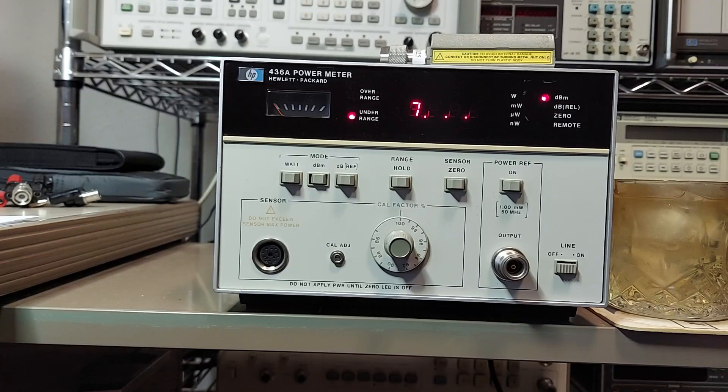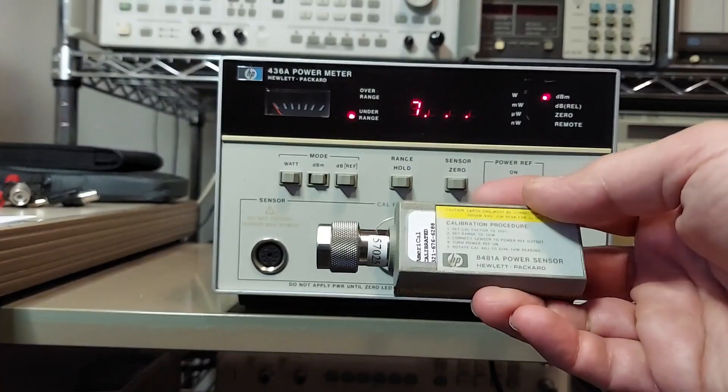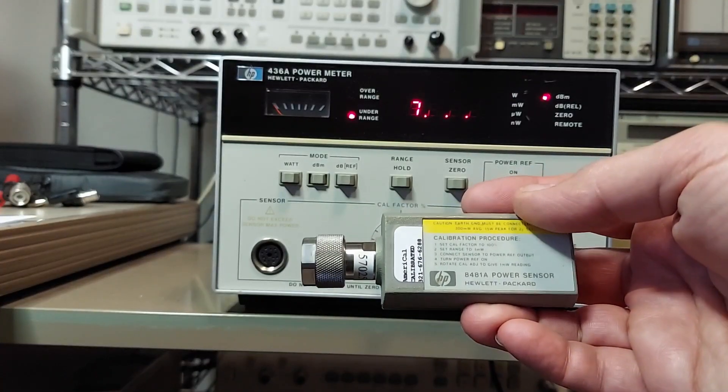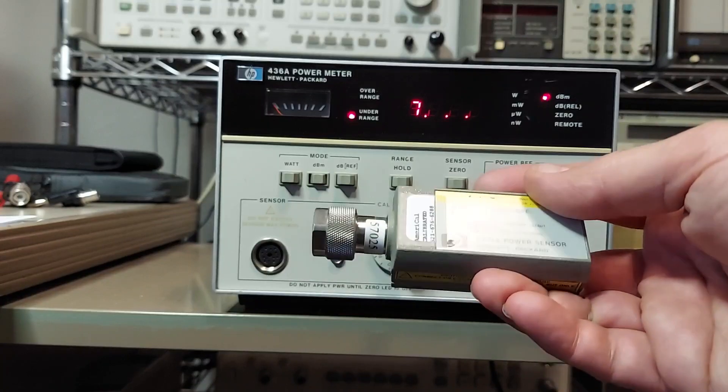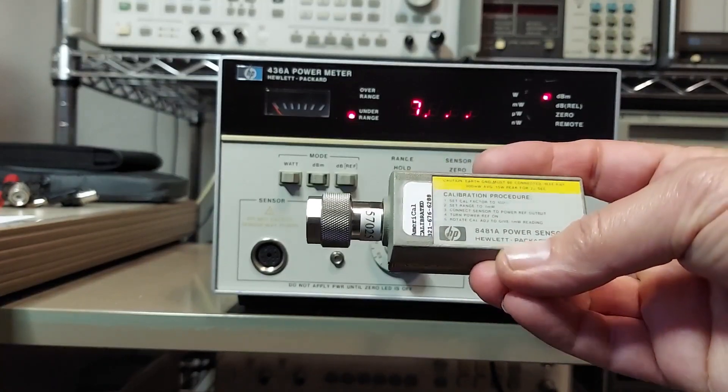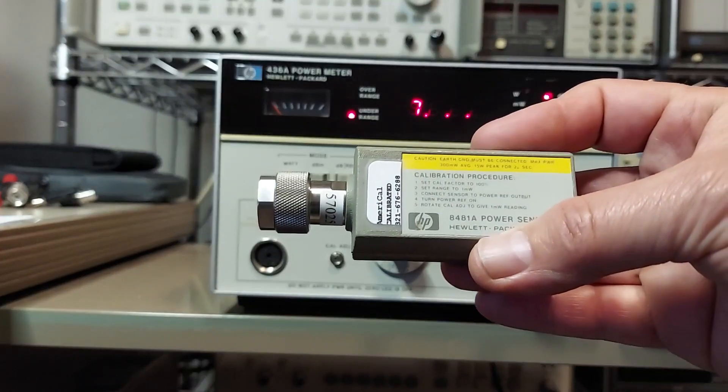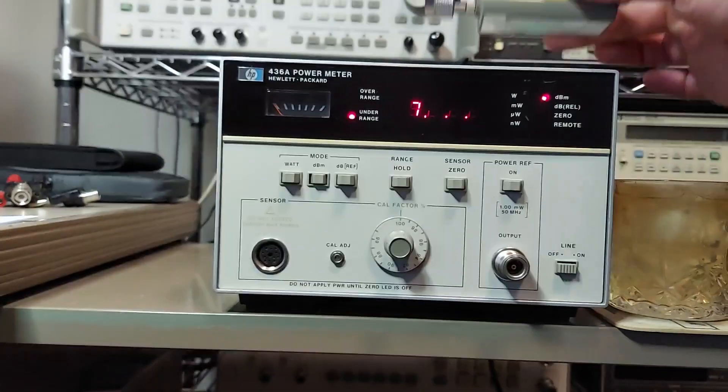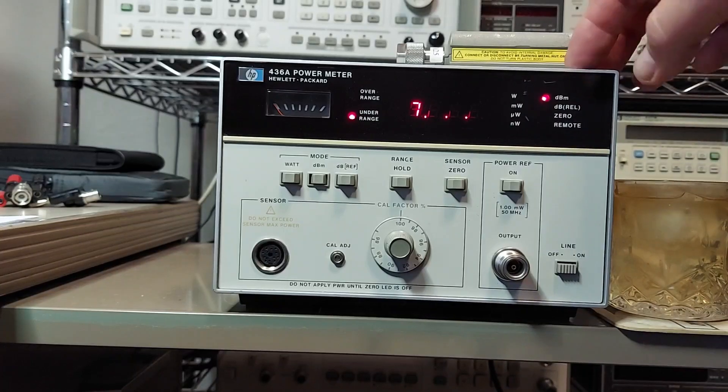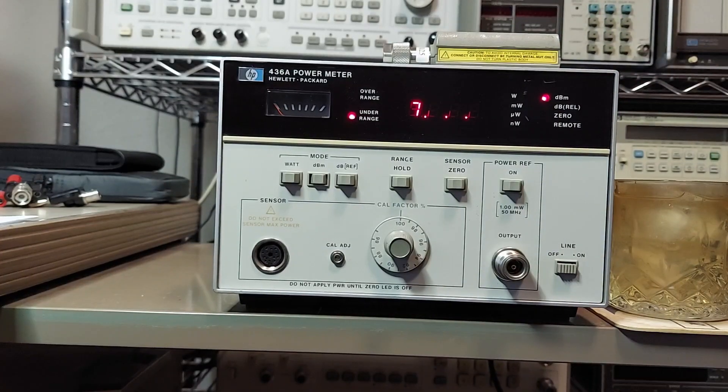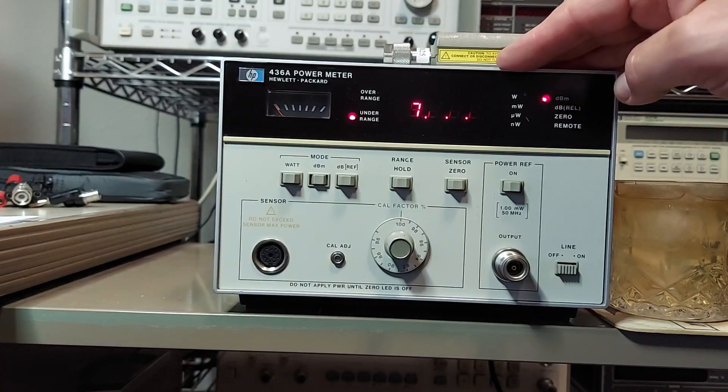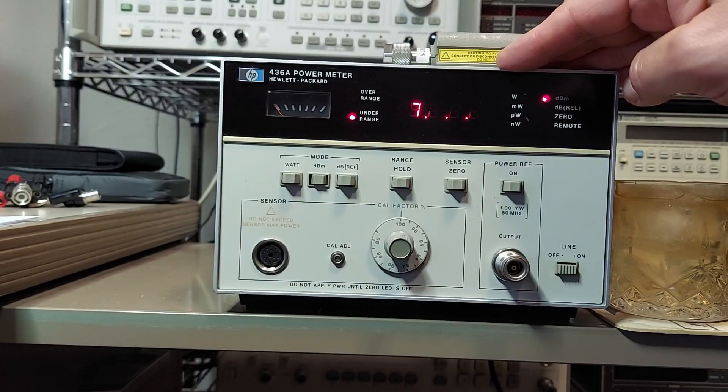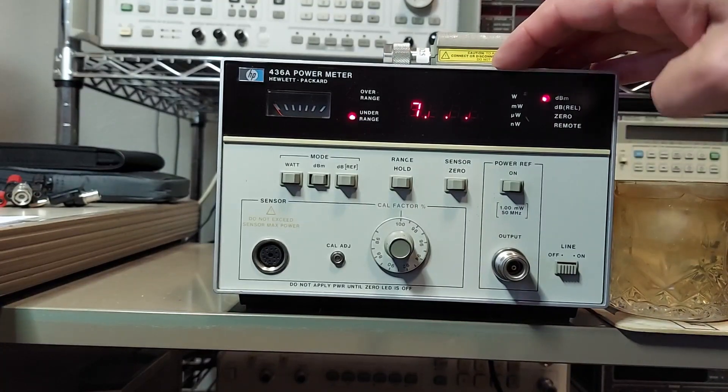They're designed to be used with these power sensors. This one here, the 8481a, covers 10 megahertz to 18 gigahertz and power range of minus 30 to plus 20 dBm. These meters can be used with these power sensors and depending on the power sensor, they can be used anywhere from 100 kilohertz to 18, 20, 50 gigs or more.